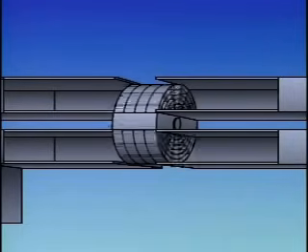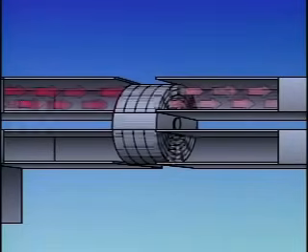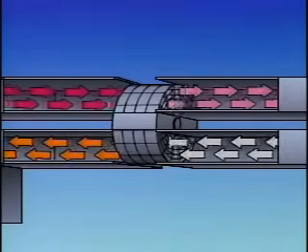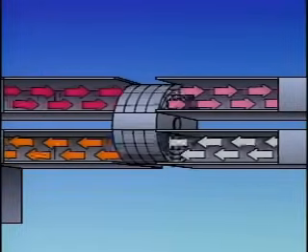As the drum rotates, the metal plates move from the stream of hot combustion gases — where the plates heat up — into the stream of cooler incoming air, causing some of the plates' heat to be transferred to the air. In some systems, steam is used in the tubes instead of combustion gases to heat the air. Regardless of the air preheater's design or the medium used as a source of heat, the heating medium and the air don't come in direct contact with each other.